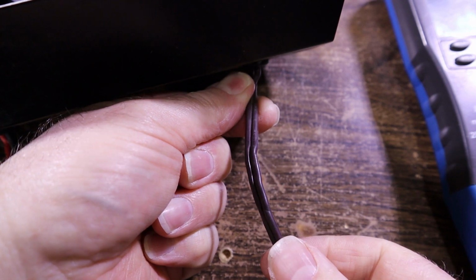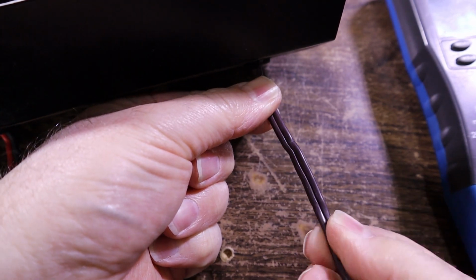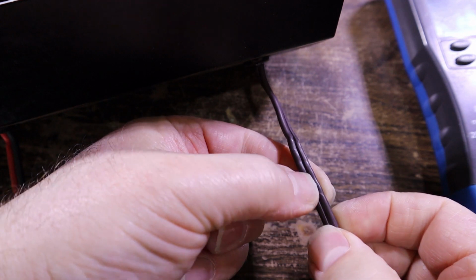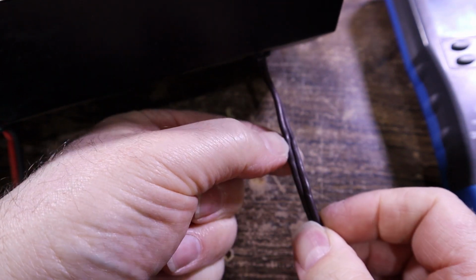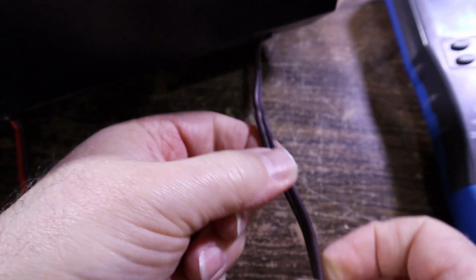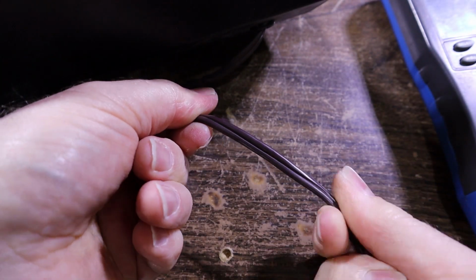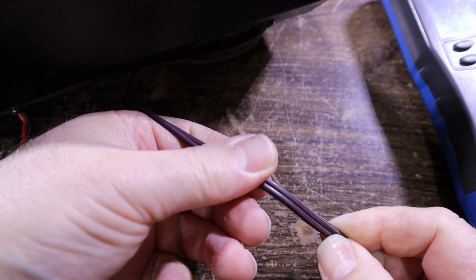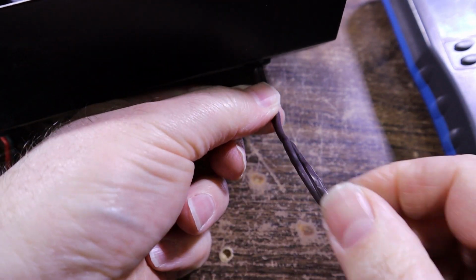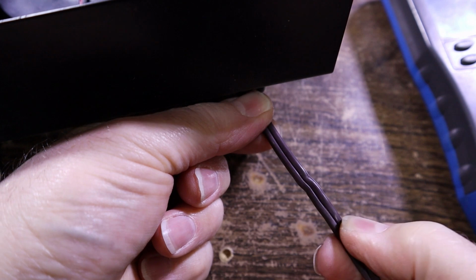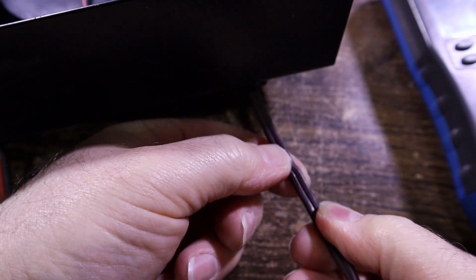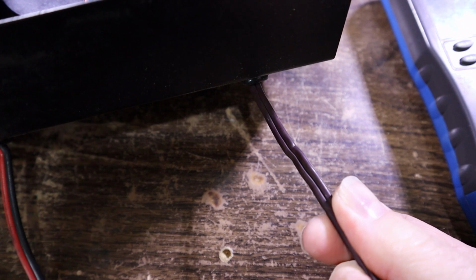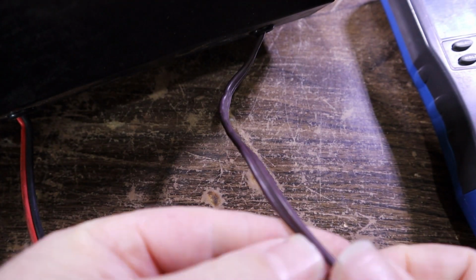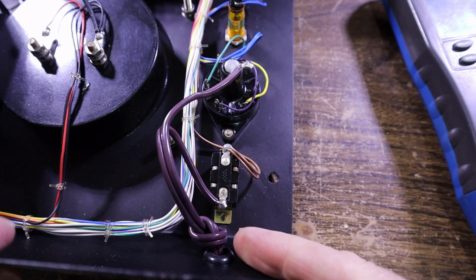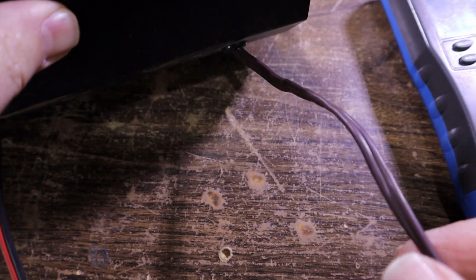One thing I noticed is that ripple effect on the cable. It's quite possible the cable is damaged right there, because it should have more of a smooth texture to it. That's almost a dead giveaway that's where our problem probably is. We have a lot of cable to work with, so I think what I'm going to do is cut it back here where it's good, test it, and then feed it back through the hole and reattach it if it's all good.